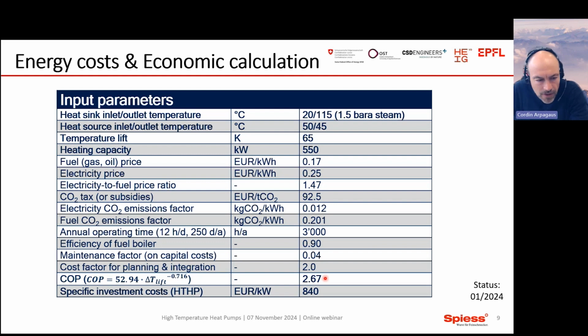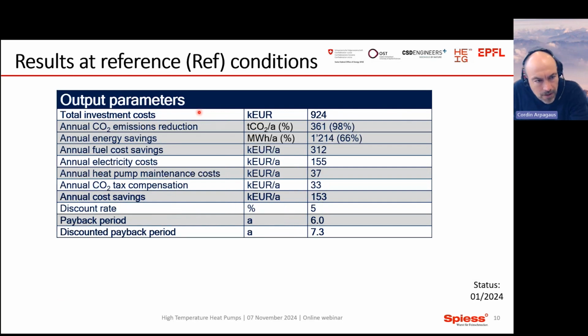So it's a good fit curve that would also fit the heat pump supplier offers, the COPs from there. And this would give then a specific investment cost of 840 euros per kilowatt. We used this as a starting point. Then as output parameters, total investment would be 924 kilo euros and could reduce CO2 emissions by 98%. So it's almost a complete substitution. Energy savings also 66%, so substantial. Cost savings for fuel and electricity costs, these are offset by the additional heat pump maintenance costs and CO2 tax.